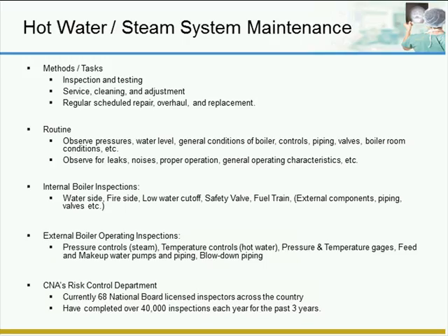It's a common known fact that a 16th of an inch of scale on the water side of a boiler will decrease the boiler efficiency 13%. The more scale, the less efficient the boilers will be. A quarter inch of scale on the boiler tubes will decrease the efficiency 38%. The scale ultimately causes poor heat transfer and could result in boiler failure. Corrosion, scale, and carryover are controlled by a water treatment program. You insert chemicals into the boiler and do proper blowdowns on the boiler, and all the impurities should be blown out.